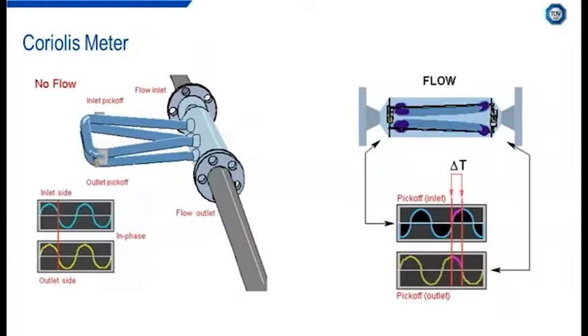So another example of our modern flow metering technology is the Coriolis meter. The Coriolis meter is becoming much more common in industry now and offers a very high accuracy option for flow metering. The main advantage of a Coriolis meter is the fact that it offers the ability of direct mass measurement as well as independent density information.